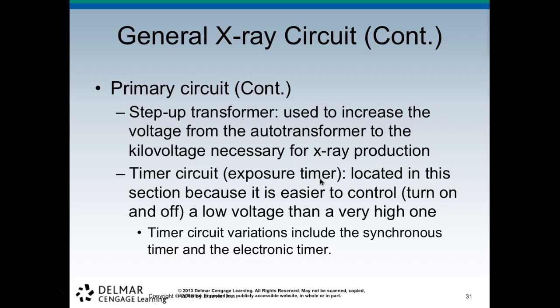Important stuff in your primary circuit: there's a step-up transformer. It is used to increase the voltage from the autotransformer to the voltage necessary for X-ray production. The timer circuit is the exposure timer, located in this section because it's easy to control, turning on and off a low voltage than a very high one. Timer circuit variations include the synchronous timer and the electronic timer.